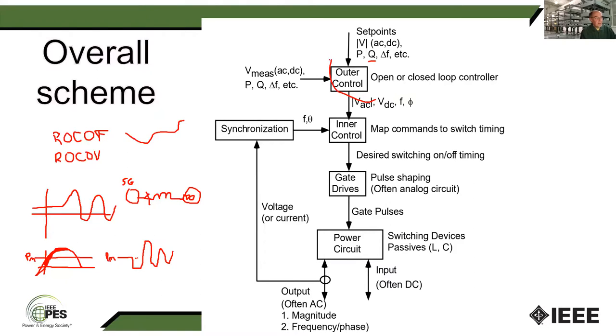And if we compare this to our P sub M, and we want to imitate this with energy storage, then if we ignore this part here and get into the response, as we go back and forth, we're going between power going out of the kinetic energy of the machine and power being absorbed by the kinetic energy of the machine. During part of the swing, the kinetic energy of the machine is decreased because it's putting extra power into the system. So this curve is really P electric, but originally P M is equal to P electric before the disturbance. Then P electric goes to zero while the breaker is open or while the three-phase fault is present, and after it's cleared, we get this oscillation.